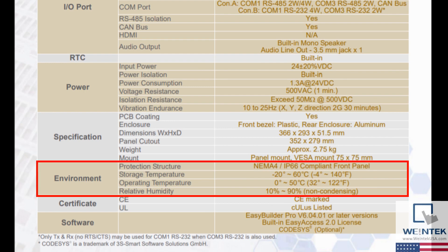Next is the environment section. This section will provide important details for storage and operation specifications. NEMA, the National Electrical Manufacturers Association, will give ratings to enclosures for electrical components. The NEMA 4 rating says that this unit is able to withstand dust, rain, snow, and hose directed water. IP or ingress protection has various ratings for products. This specific model has a rating of IP66 which protects against hose directed water, rain, or snow. It is not intended to be submerged in water.